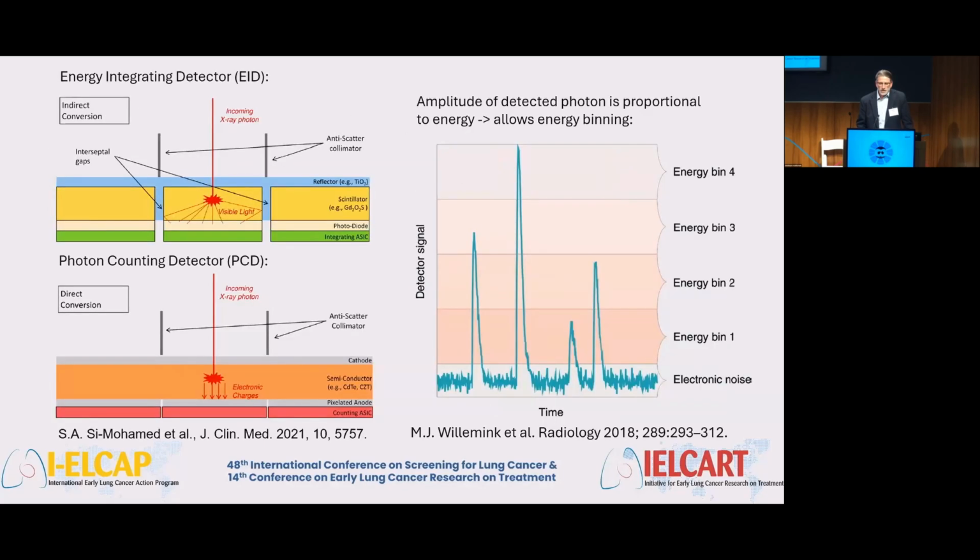And then more recently, advances in photon counting. There's two ways that photon counting enables better contrast and lower noise. One is that you can actually quantify the energy levels of the detected photons, because now you're using a detector that, instead of approximating that energy through light, which is then radiated out and then a photodiode picks up that light, you're actually physically detecting each photon coming in. This enables you to threshold out the noise level, and then subsequently eliminate that.